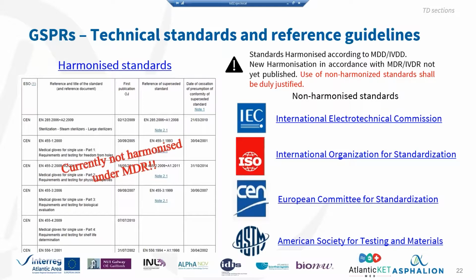It is true that there are standards that are planned to be harmonized under the regulation, but it has not happened yet. They have not been published yet. Okay, so take into account that these harmonized standards are harmonized under MDD, not MDR.